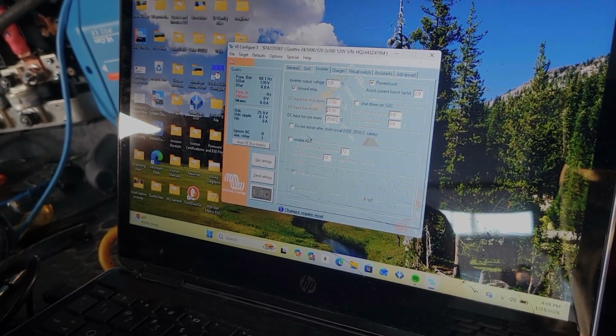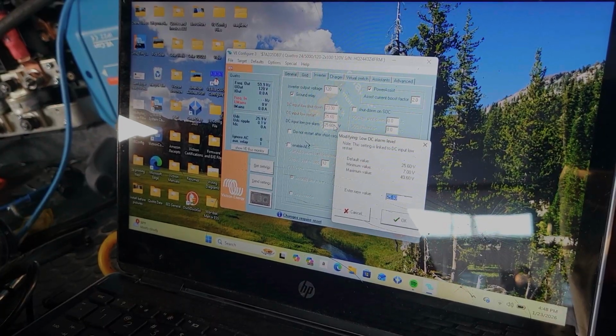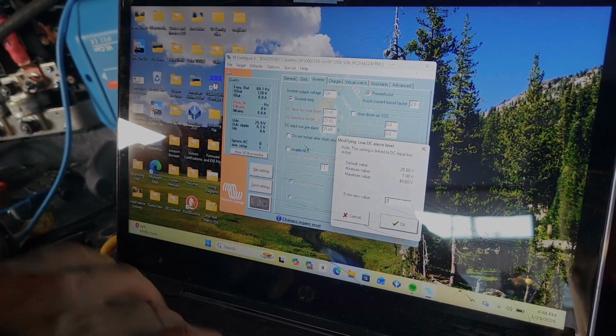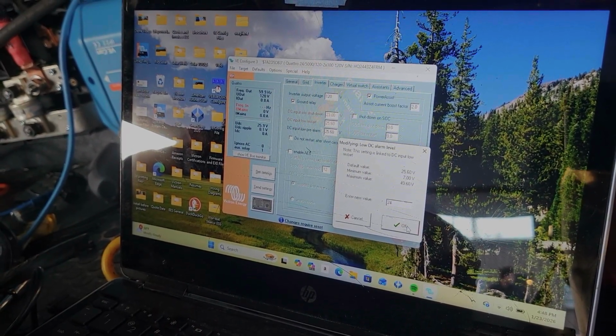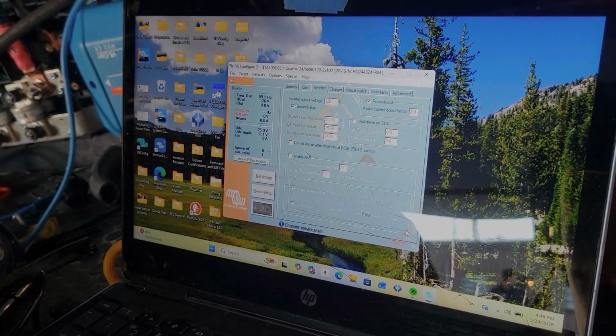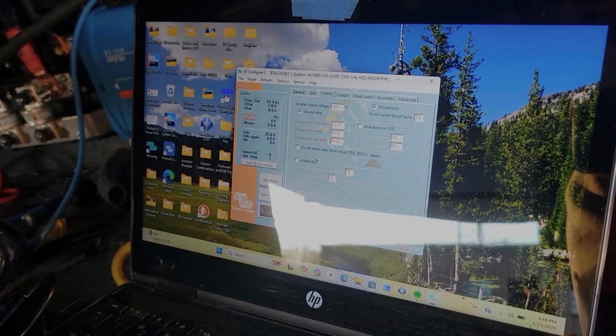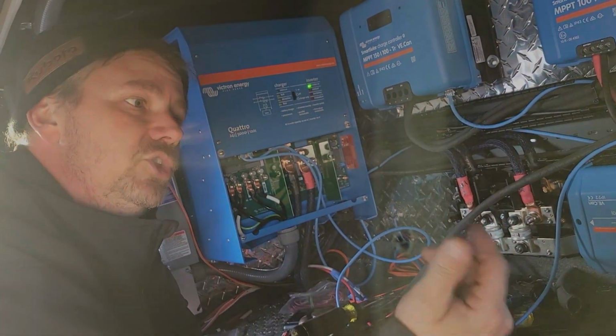Now we want to do the pre-alarm. The pre-alarm is when these inverters come on and they tell you, hey, our batteries are about to shut down. We're going to do that at 24. So at 24 volts, that's when these inverters will start blinking this light and telling you low battery. You also get a warning on your touch screen saying, hey, your battery's low. You are very close to shutdown at that point.